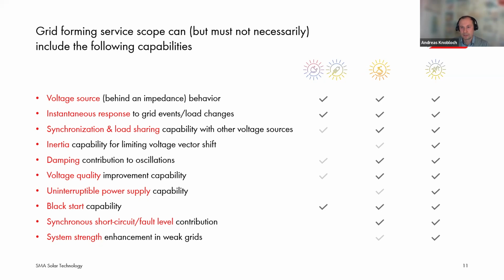It is also the instantaneous response to grid events or to load changes, the capability for synchronization with other voltage sources and for load sharing, capability to provide inertia for limiting voltage vector shift, capability for provision of damping to oscillations that occur in the grid. That might have different reasons. Of course, own damping is always required, but here it means the damping that is needed for oscillations that result from interactions in the grids.